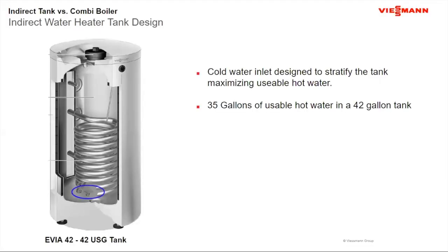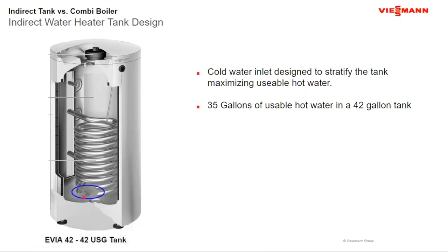Okay. Now, a couple other things come into the design of the water heater that help from that flexibility standpoint. I want to minimize the number of times the boiler is cycling to maintain temperature in the indirect water heater or to keep up with the water heater demand as needed. So a couple of things come into this. I want to maximize the amount of usable hot water in here. So I look at tank design, usually there'll be something in the bottom that diffuses the water coming in to maintain stratification in the tank.